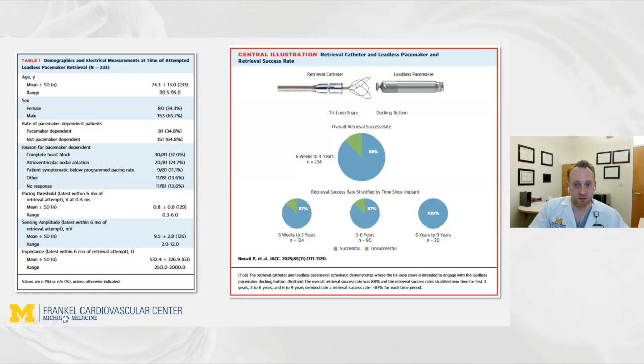In the AVEIR system, you grab it and you have to counterclockwise torque it to release the active fixation helix. And that requires a specific catheter. Again, we'll go into that a little bit later. So these are data from the AVEIR/NanoStim experience. Again, this is newer data. This is actually going to be published in a week or two in JACC.